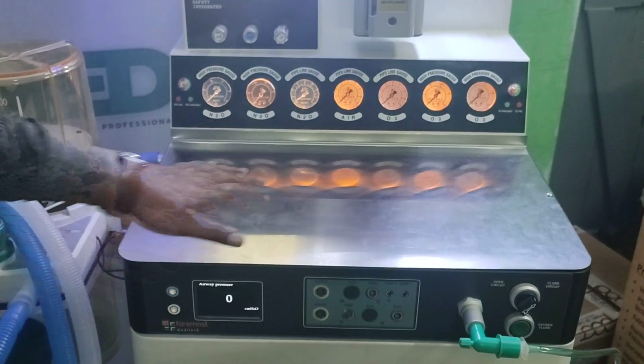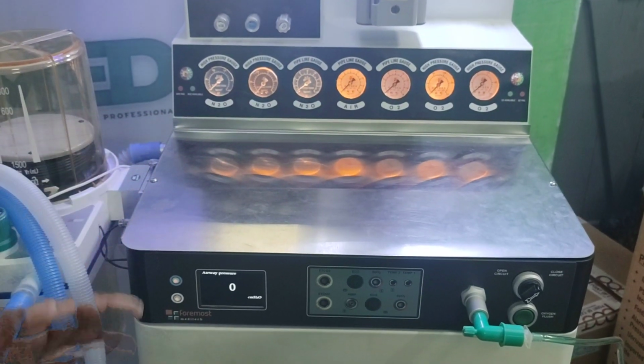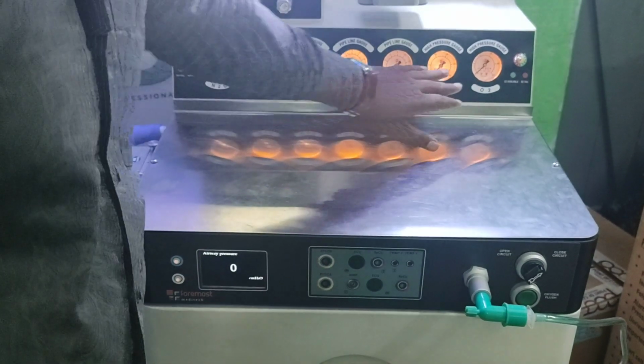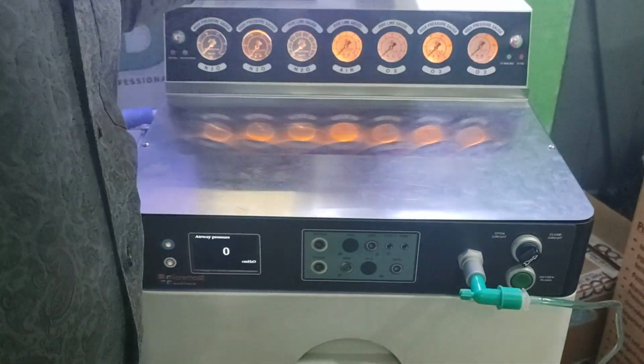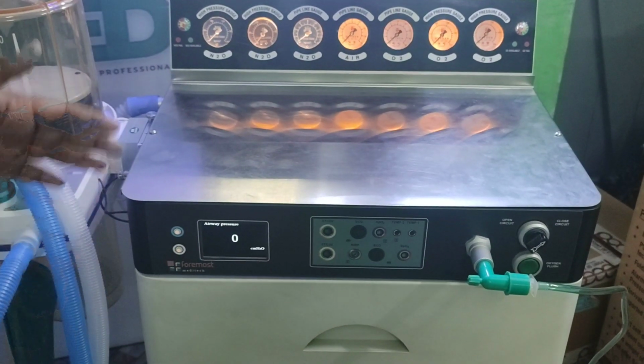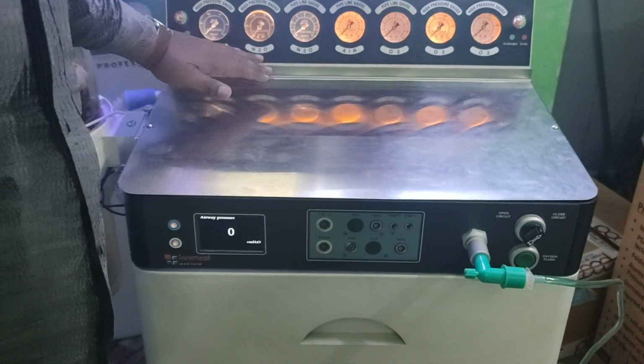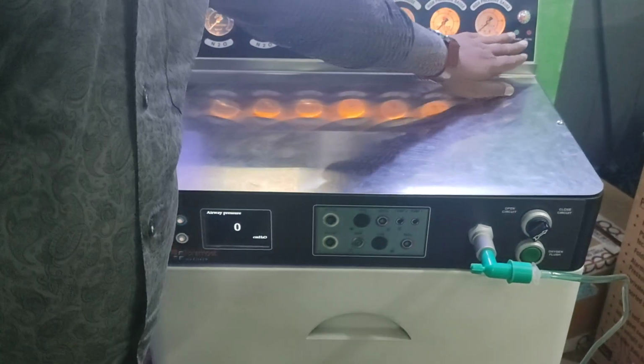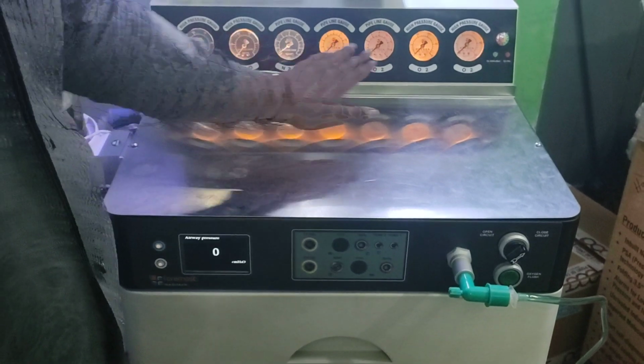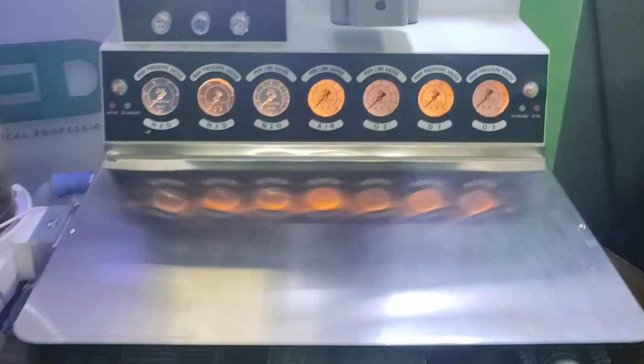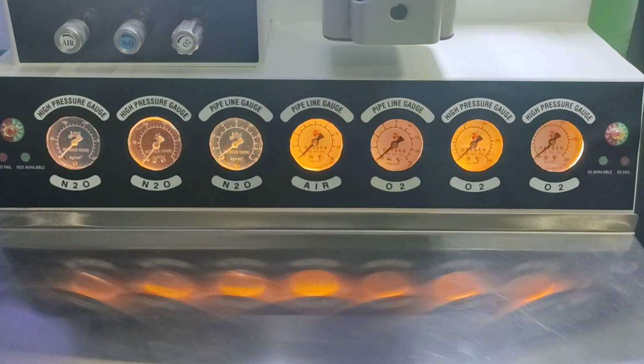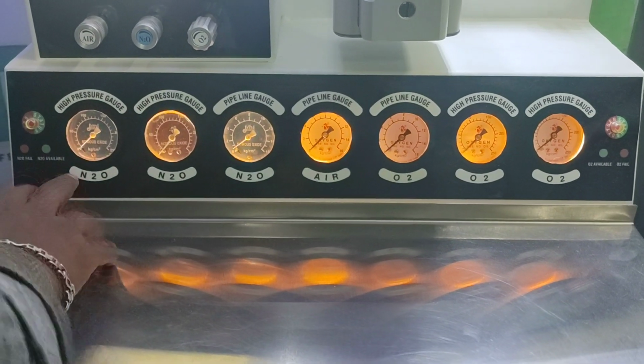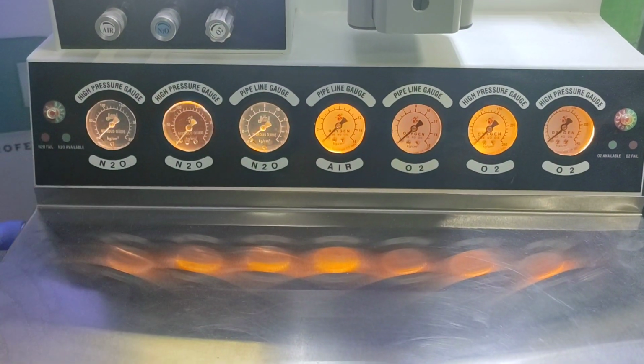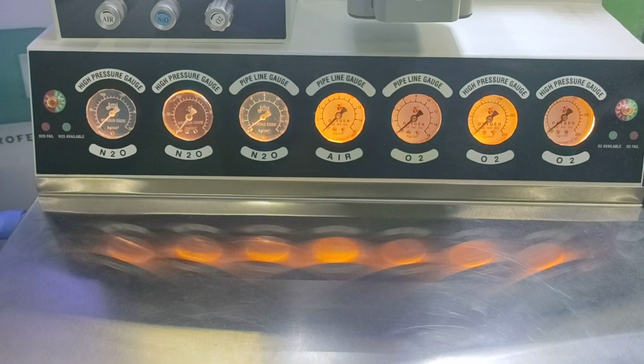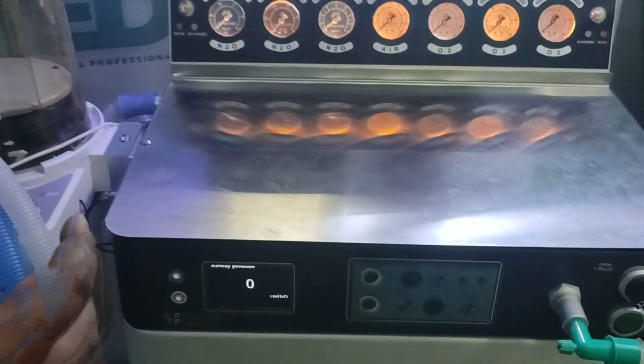All the functions and all the meters are there. You can check whether the supply lines have oxygen pressure, or whether the cylinders you have put beside have cylinder pressure. All the cylinder pressures are here, and there are also alarms: an N2O alarm and an oxygen alarm. If the pressure is low, or if there is no oxygen supply, the alarms will glow here, N2O fail, O2 fail. So you will be sure that your supply lines are okay.